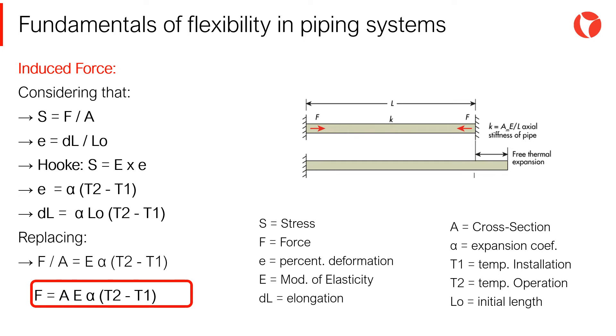To get an idea of the magnitude of the forces that can be induced in a piping system, consider the following example: a 10-inch NPS schedule 40 pipe, restricted at both ends, installed at 20 degrees Celsius and with an operating temperature of 115 degrees Celsius, develops an internal force of approximately 200 tons. This load is transmitted to the ends of the pipe and must be withstood by supports, structures and/or equipment nozzles.